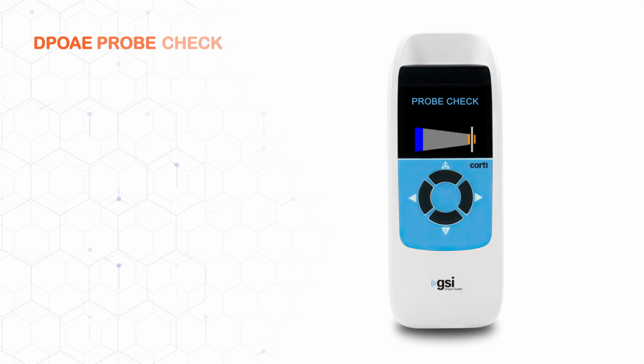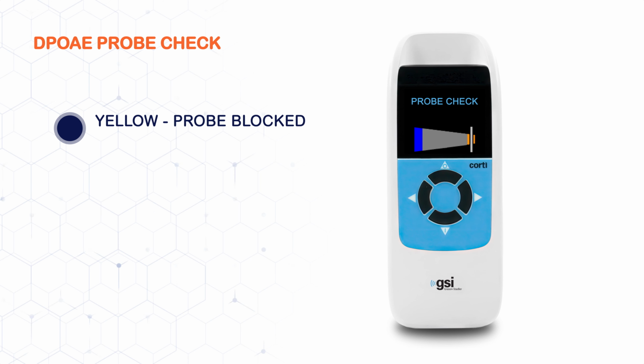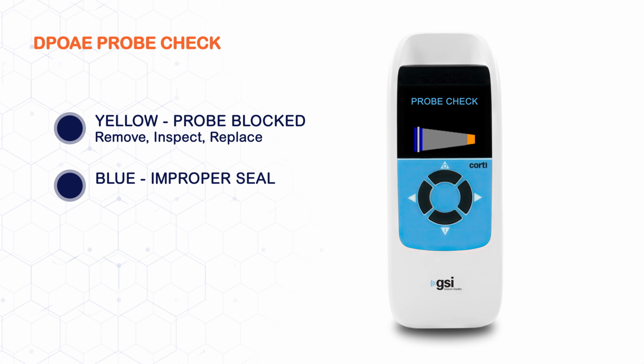If the white line is in the small yellow area of the cone, the probe is blocked. It should be removed, evaluated for debris, and replaced into the ear canal. If the white line is in the large blue area of the cone, there is not a proper seal, and the probe should be adjusted to ensure a tight fit. At this time, you may need to change the ear tip to a larger size.